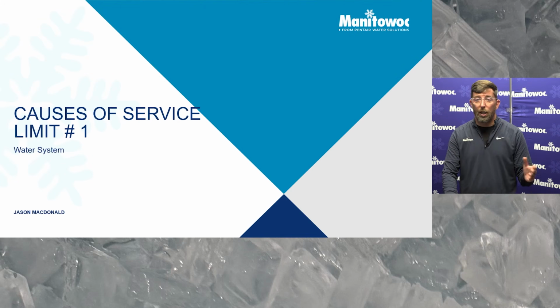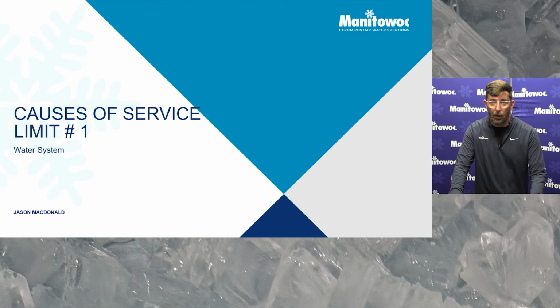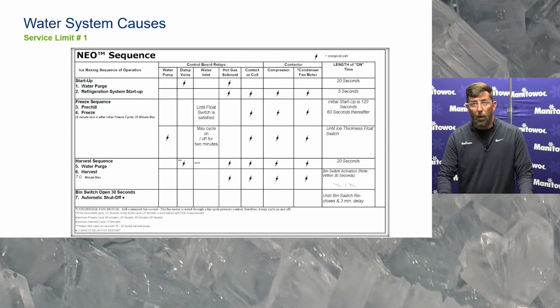All right, so we're going to talk about causes of service limit number 1. We're not just telling you what it is, we're going to tell you a little bit about what could cause things. And we're going to start with the water system. Now keep in mind, we talked about 3 service limits. I'm probably going to allude to a different service limit while we talk about the water system. So our sequence of operation is up there, just letting you know what's supposed to be energized when. It's a good idea to know what the ice machine is supposed to be doing, so that way you know, is everything okay? Are you troubleshooting the wrong thing?